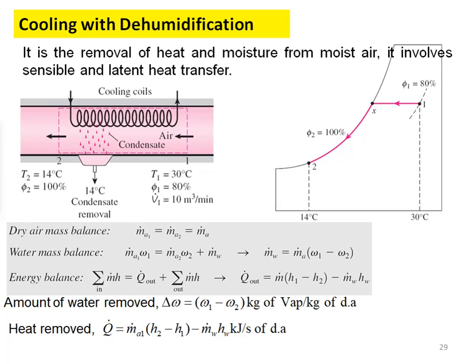The first combined process is cooling with dehumidification. Here, along with sensible cooling, we are going to dehumidify the air — that means we remove the moisture content present in the atmospheric air. This cooling coil has a larger surface area than in sensible cooling. When the cooling coil surface temperature is less than the dew point temperature of the air at the corresponding pressure, condensation starts.